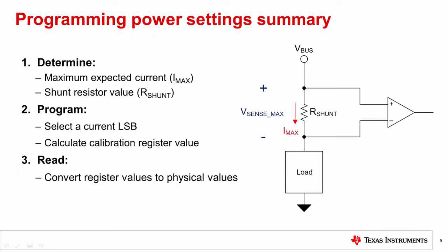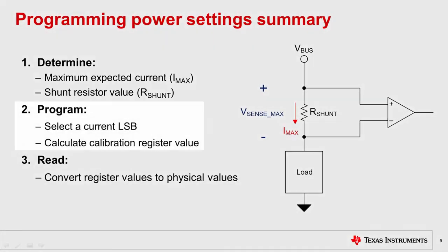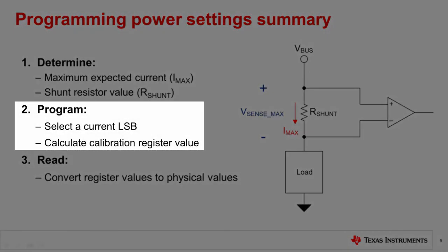Let's take a minute to summarize what we've learned in this video. Taking advantage of TI's digital power monitors is a simple three-step process that can be called determine, program, and read. Specifically, step one is to determine the system requirement: find out what is the maximum expected current and which shunt resistor to use. Step two is to calculate the current LSB and select the smallest whole integer that is larger than the calculated value. This provides the best compromise among resolution, accuracy, and ease of calculation.